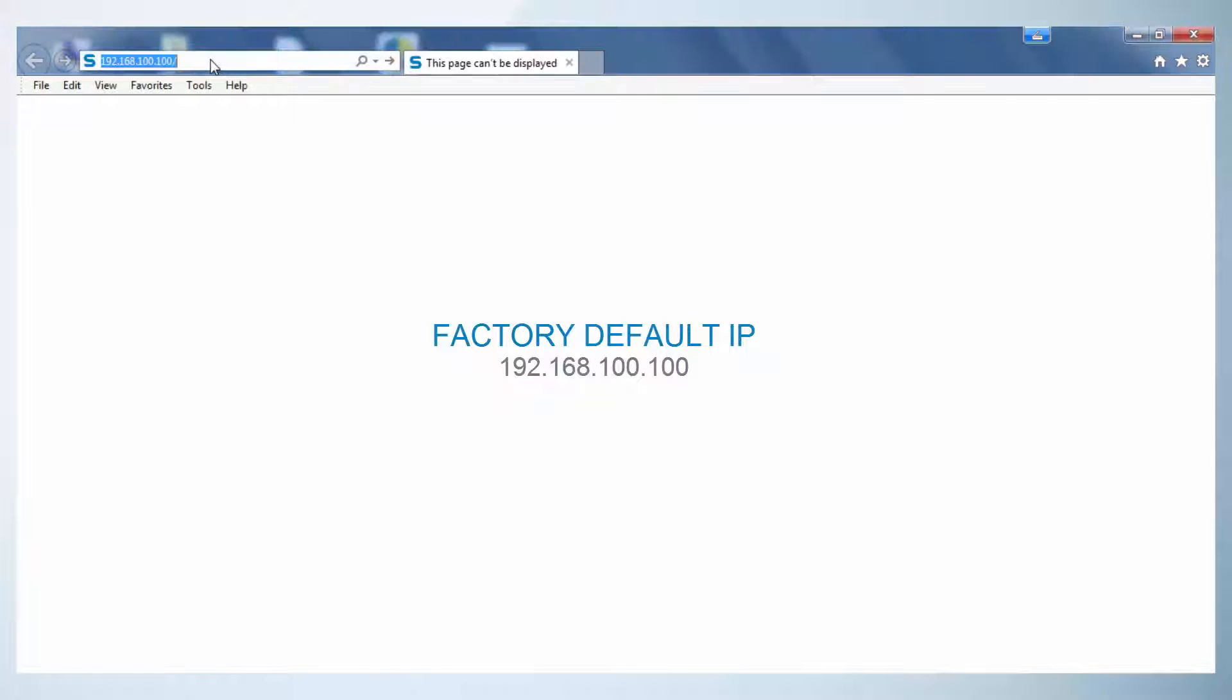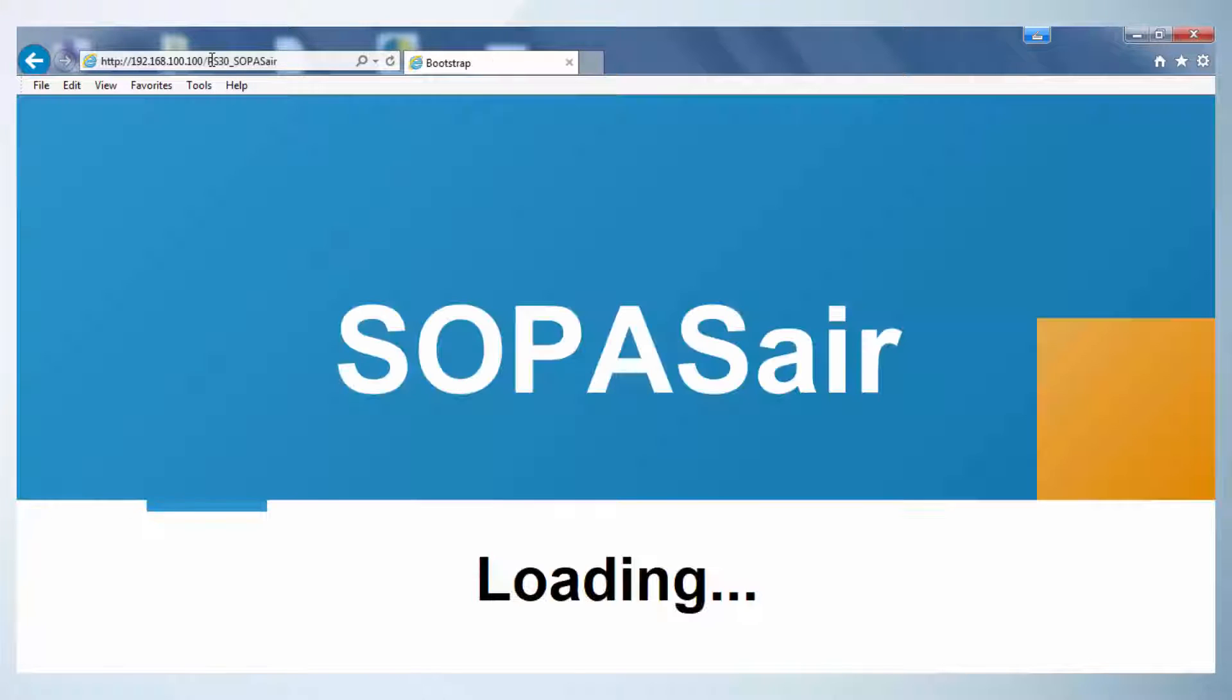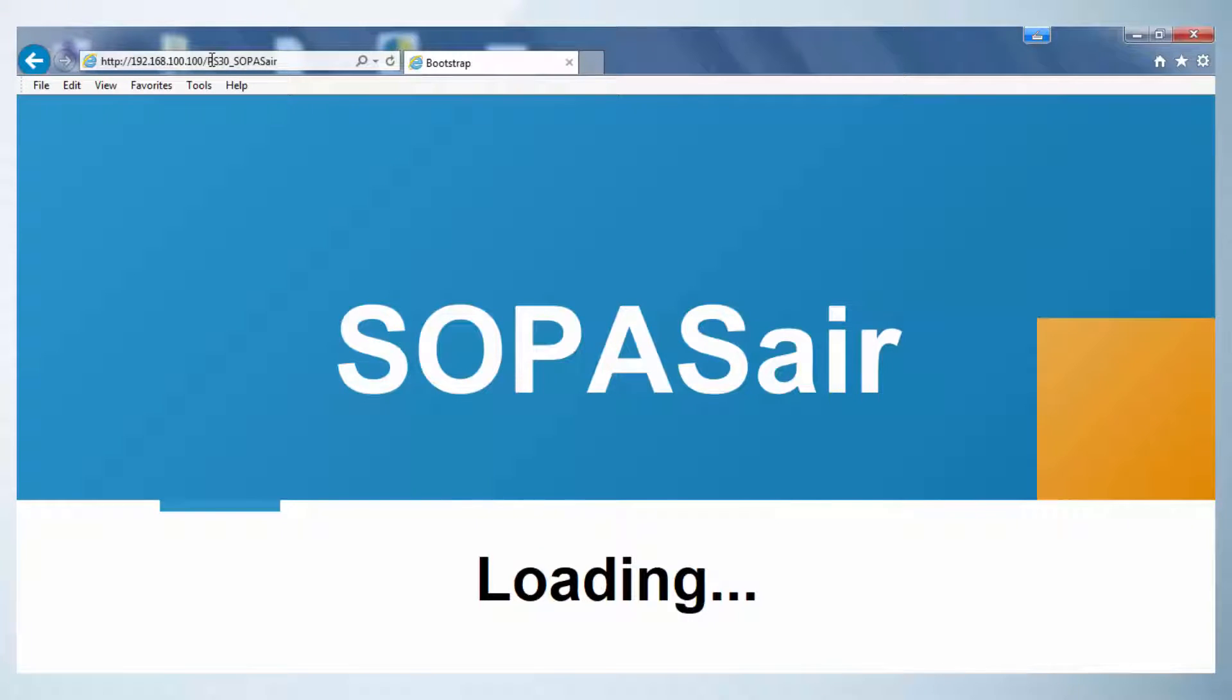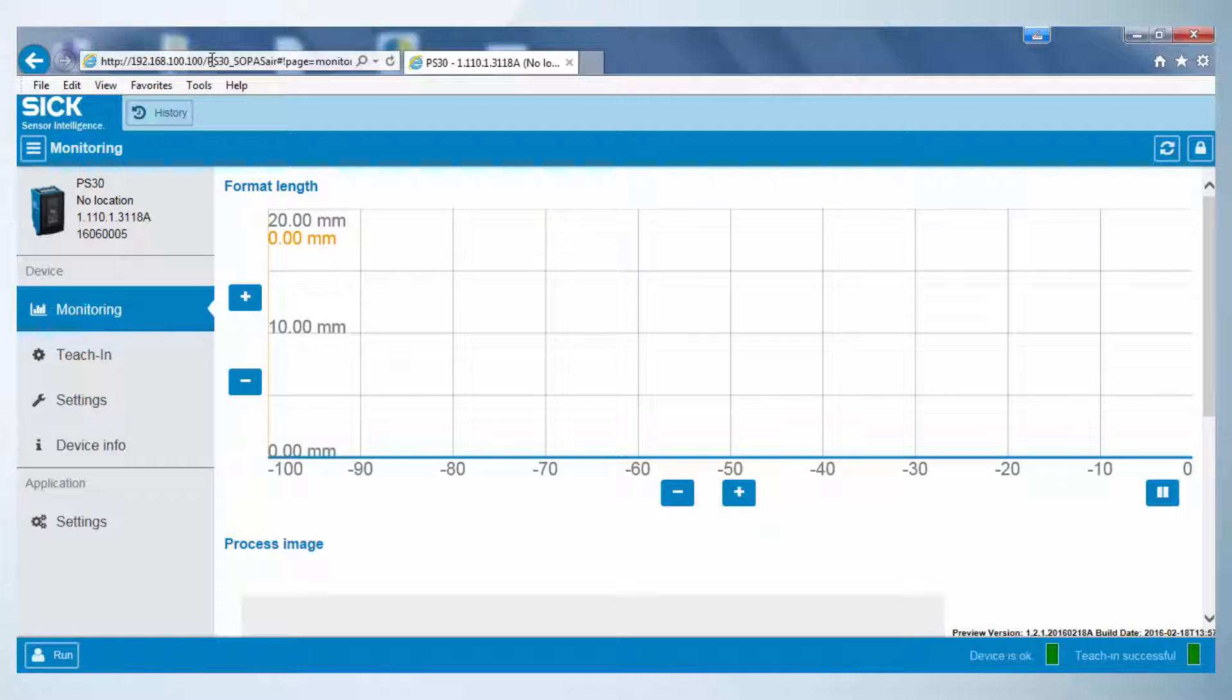To start Sopas Air, a standard web browser has to be started. By typing in the sensor's IP address, Sopas Air is started. In a factory setting, the default IP address is 192.168.100.100. The integrated web server contains the software Sopas Air, which is started now automatically in the web browser.